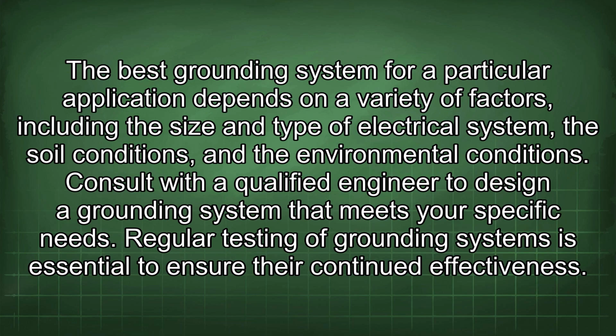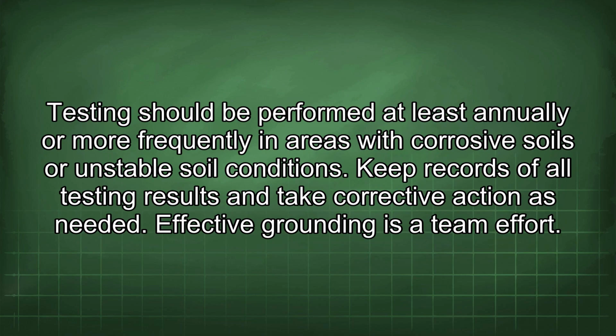Regular testing of grounding systems is essential to ensure their continued effectiveness. Testing should be performed at least annually or more frequently in areas with corrosive soils or unstable soil conditions. Keep records of all testing results and take corrective action as needed.